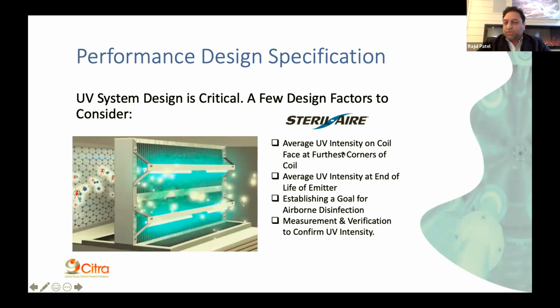We look at average UV intensity on the coil face at the furthest corners of the coil when first designed, and more importantly, at the end of life of the emitter. Just like a fluorescent lamp, the UV emitter has a depreciation curve. So we design at the lowest output, to ensure that during its 12-month life we never fall below our design targets.